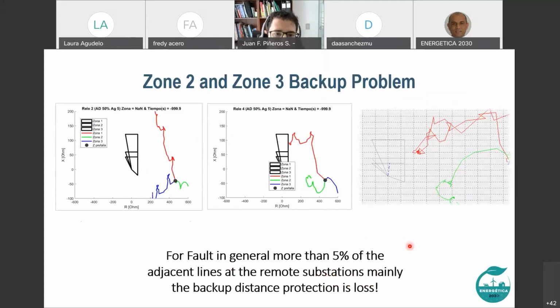Another general problem we are observing is that for faults beyond 5% location in the remote, adjacent lines, in general, when we go to 10%, 50%, 99% of the remote lines, we lose the backup of zone 2 and zone 3 of the distance protection. It means, in the topology we saw, if we have a failure in, for example, Cuestecita Scopei 500 kilovolts, in general more than 5%, then the distance protection at D1, the location we were discussing, will not be able to see it. We were simulating many cases, even a fault in a double circuit line, and we will have problems with the backup distance protection. Then we have to think about how we will provide a backup in these cases.